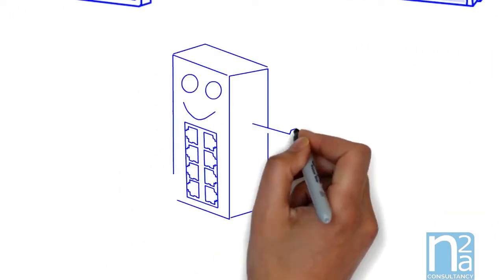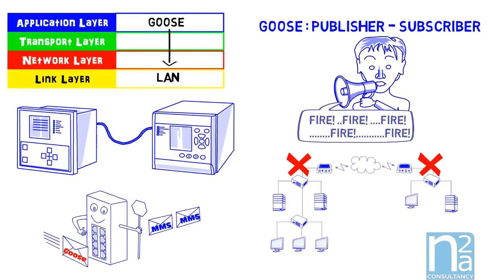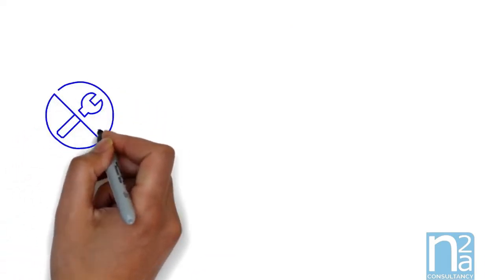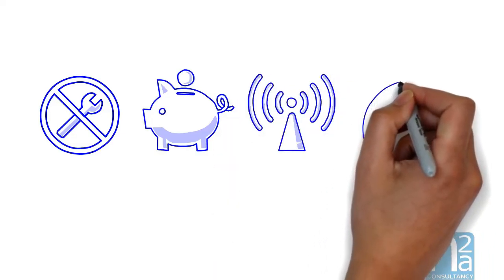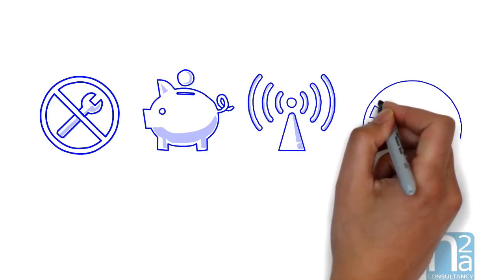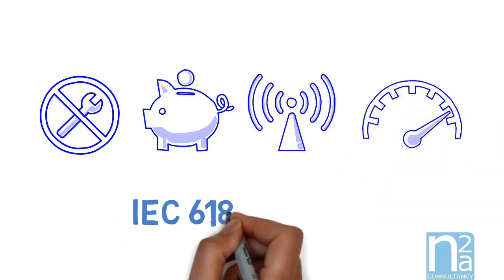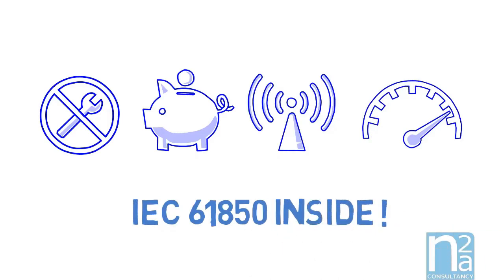GOOSE messages have a lot of advantages compared to hard-wired connections. They are easy to configure and reconfigure without rewiring IEDs. One fiber optic connection is cheaper than tens of copper wires. EMC and EMI sensitivity is dramatically reduced. Messages are delivered quicker than with wire connection, 4 milliseconds compared to at least 10 milliseconds. But to work correctly, IEDs should be designed for it, not converted to it.